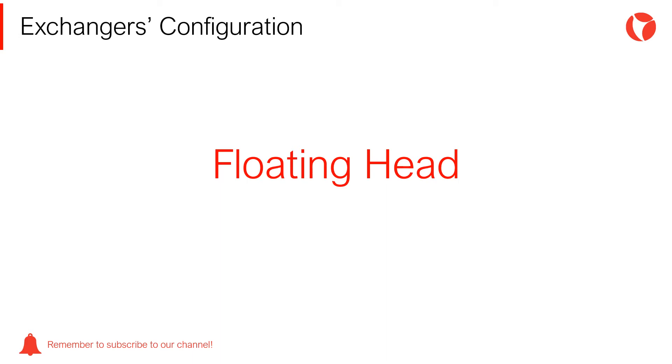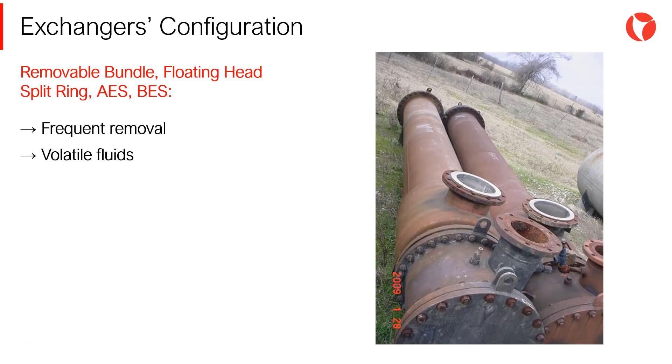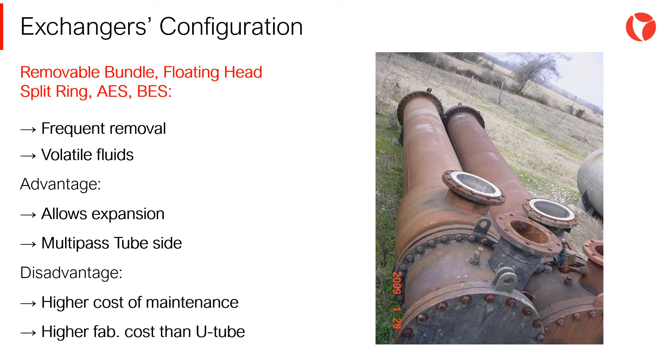And last but not least, the floating head heat exchangers. These types are a mixture of the two previous types. This configuration is the best option for inspection, maintenance and repair. The main advantages are that they allow thermal expansion and can allow multipass tube-side configurations, from 2 to maybe 12. On the disadvantage side, we find higher cost of maintenance and higher fabrication cost than the U-tube type.